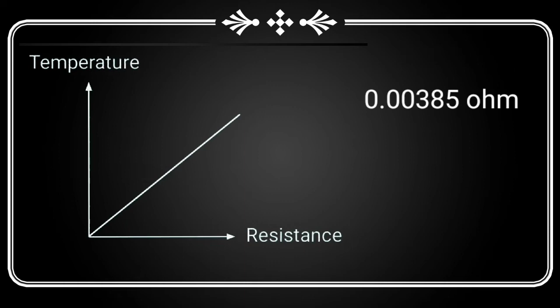Platinum resistance thermometers, or PT100, measure temperature by using resistance change to denote the temperature value. PT100 resistance at 0 degrees Celsius is 100 ohm and 138.5 ohm at 100 degrees Celsius. The resistance value increases proportionally with temperature, at 0.385 ohm for every 1 degree Celsius increase.